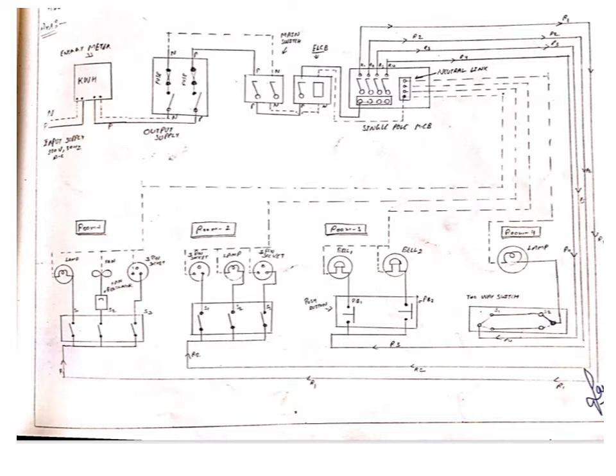So from the main switch, that is the two-pole MCB, phase and neutral will go to the ELCB, the earth leakage circuit breaker. Then from the earth leakage circuit breaker, the phase will go to the bus bar, as you can see in the connection, and the neutral will go to the neutral link. When we have given the phase to the bus bar, you can get the phase connection to all the other subcircuits also, as they are internally connected. And the neutral will go to the neutral link, so we can take the neutral output from that neutral link.